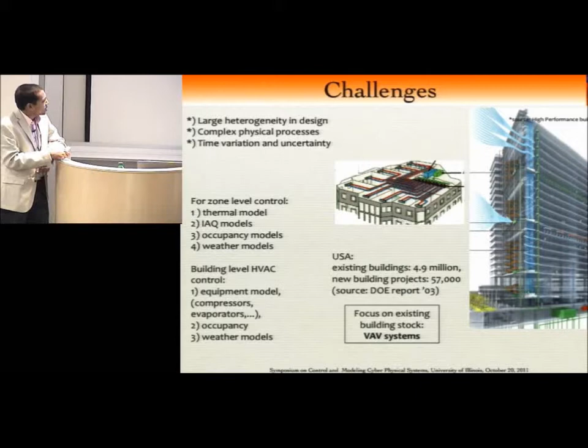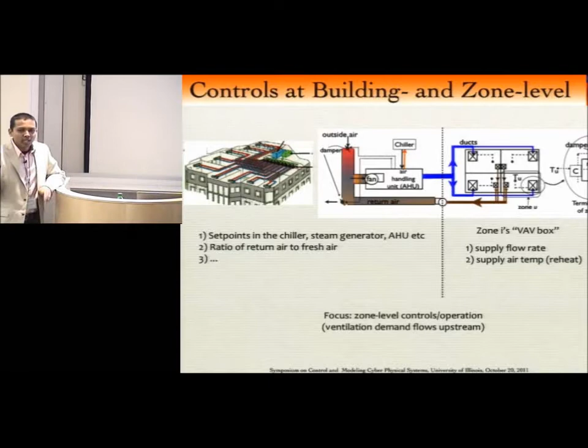The amount of fresh air you have to supply to a particular zone depends on the worst case scenario inside that zone. So suppose the whole building is empty except this one room, which is completely full. You might say the building is operating at 5% of its peak design conditions, so you should be able to use a lot of return air and only a little outside air.